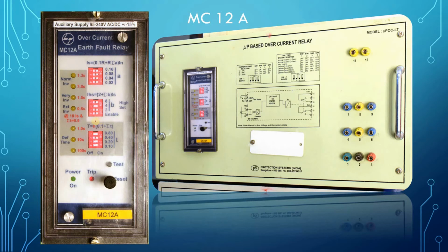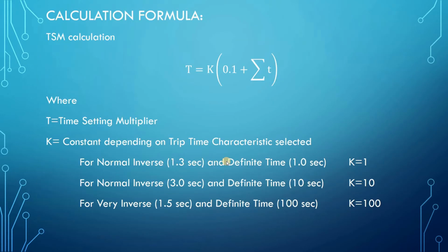But what is K? K is nothing but a constant, and this constant is decided by the characteristic set. As you can see, for different values of K: K is 1 for normal inverse 1.3, for definite time 1 second K is 1, for definite time 10 second K is 10, and for definite time 100 second K is 100.